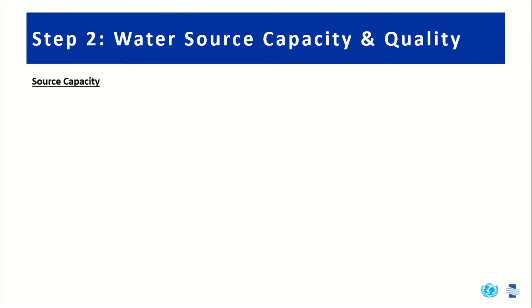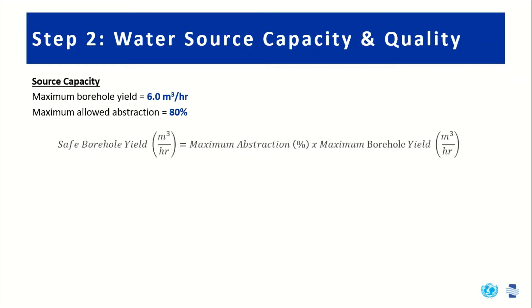For this project, there's a new borehole that was drilled and the yield test revealed a maximum borehole yield of 6 cubic meters per hour. However, in this region, there's an imposed limit to the percentage that we can extract from that total maximum yield, which is 80%. So, in order to calculate the safe borehole yield, we'll multiply the maximum extraction percentage by the maximum borehole yield to get 4.8 cubic meters per hour.